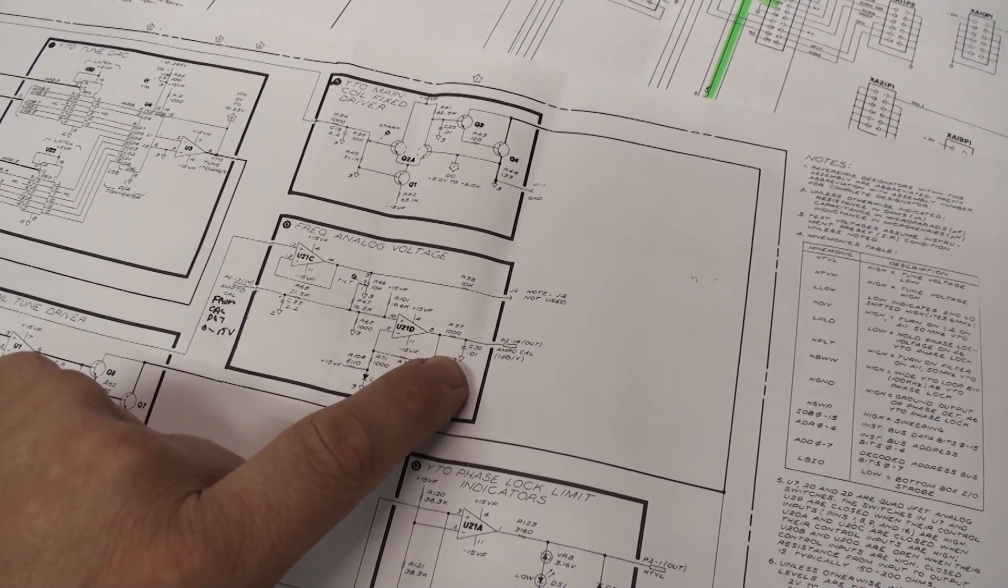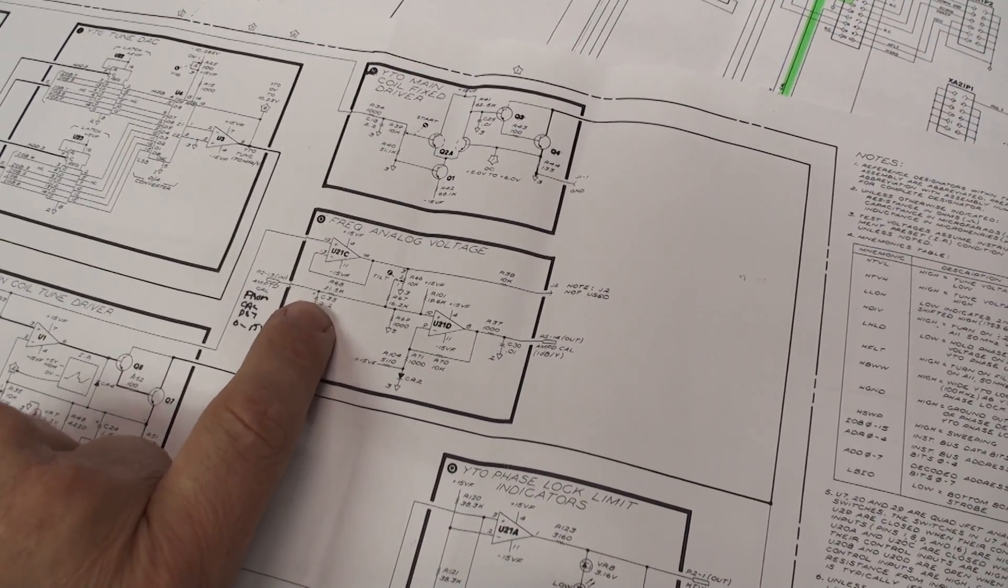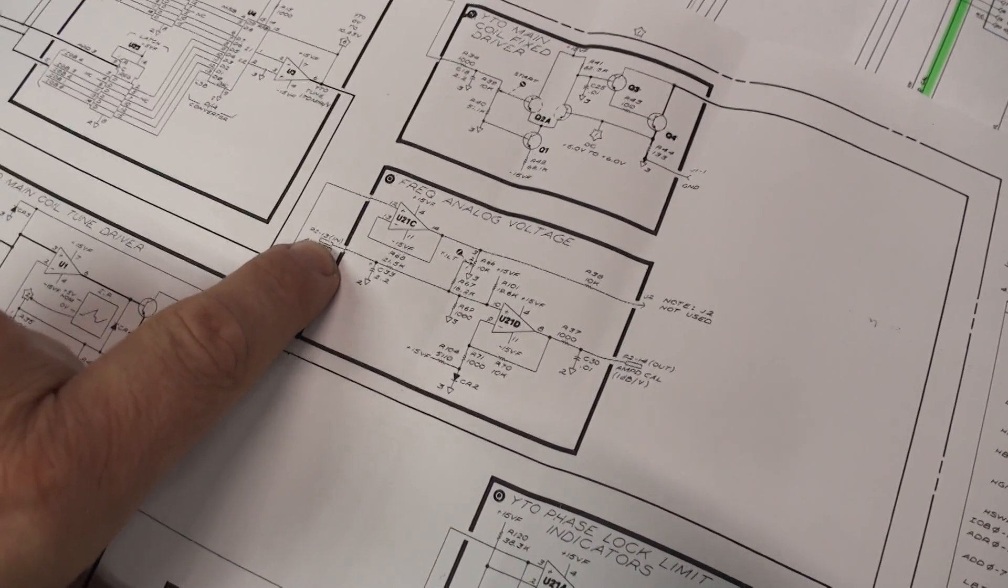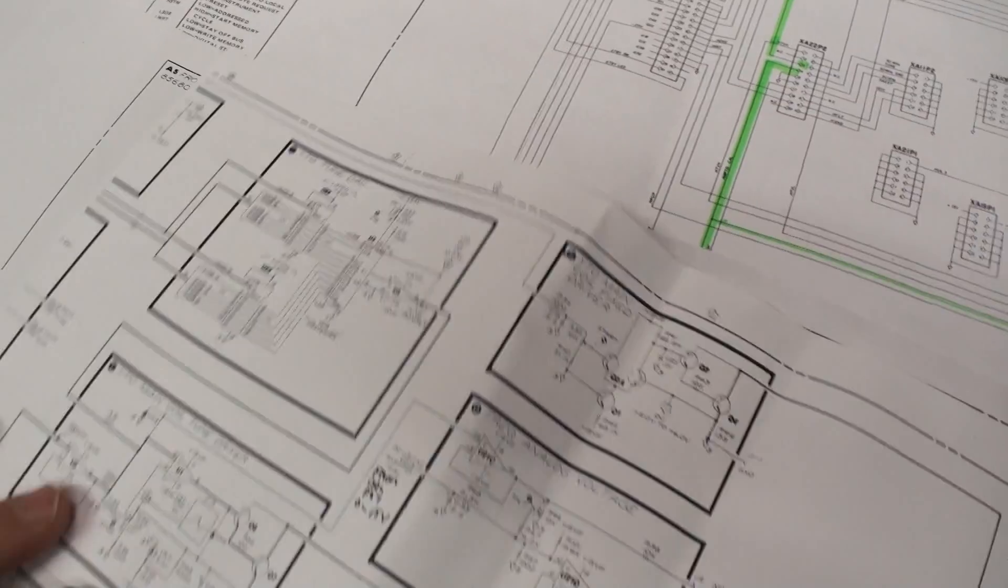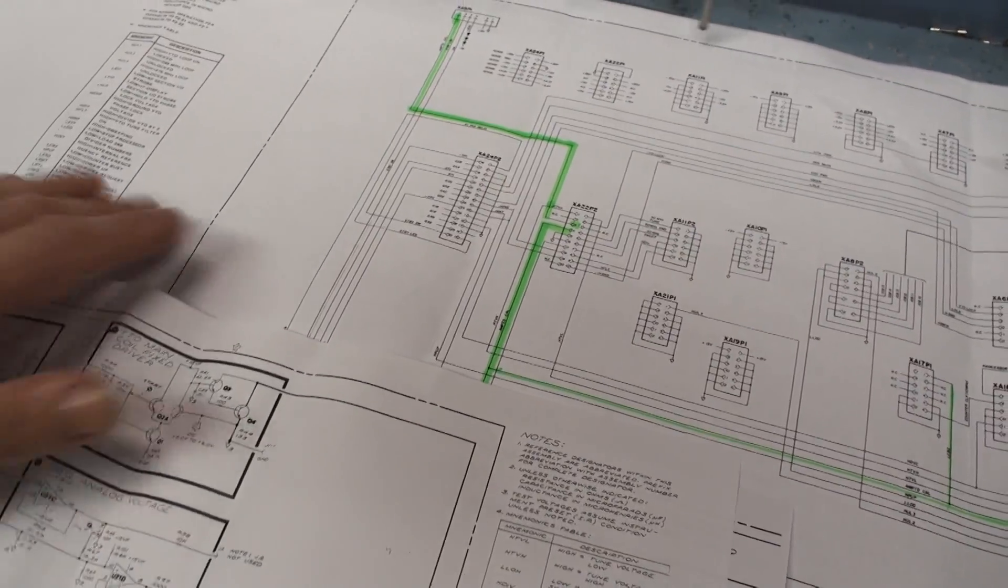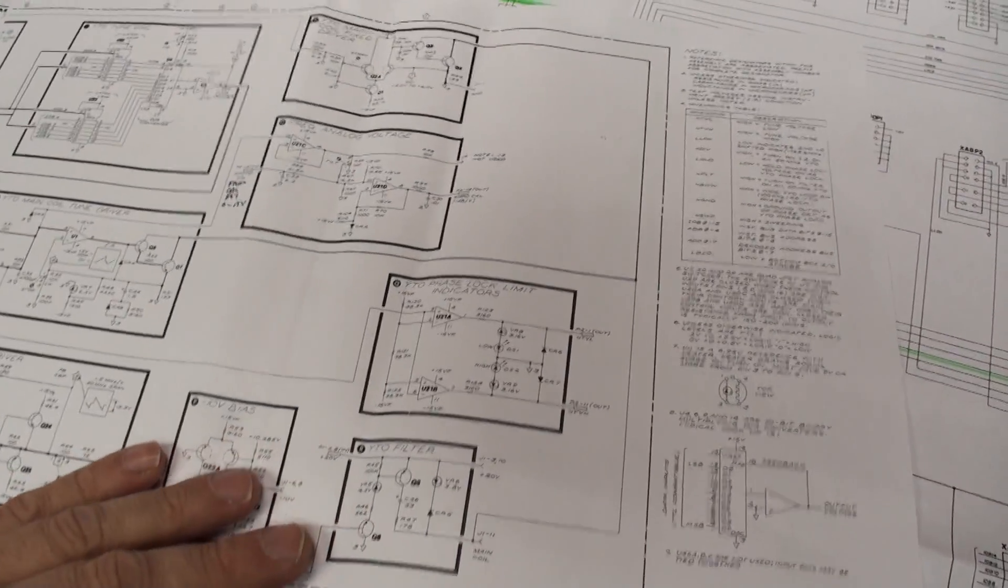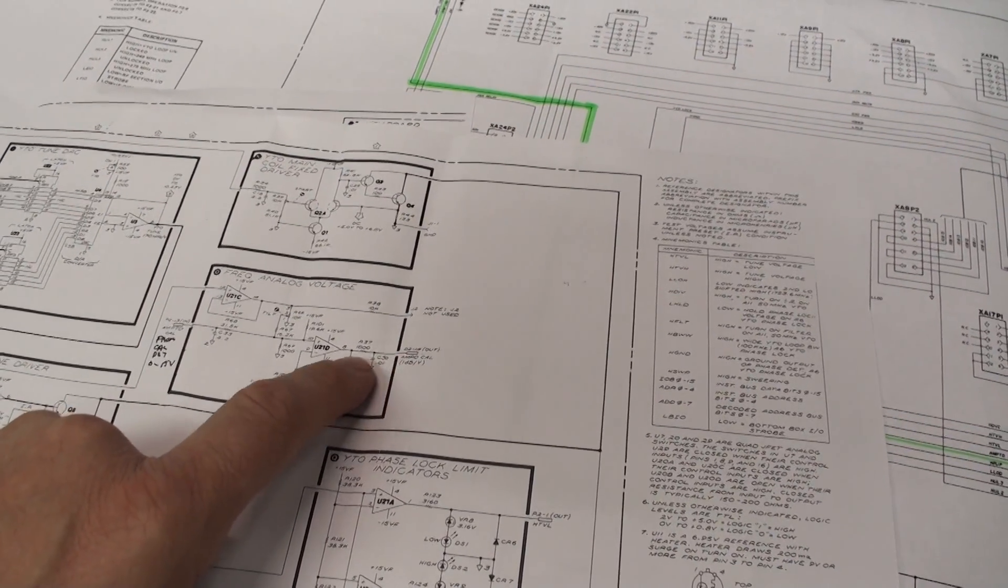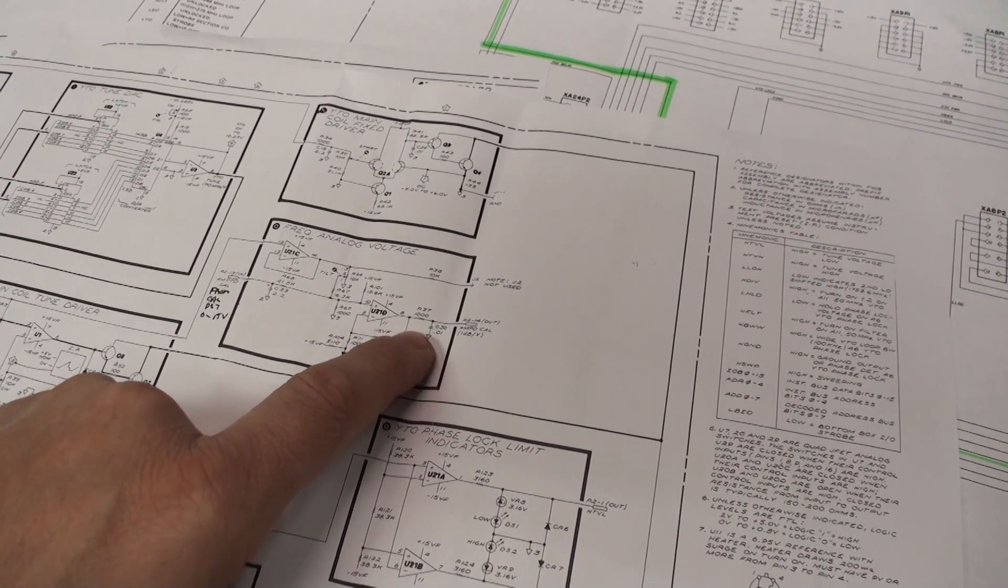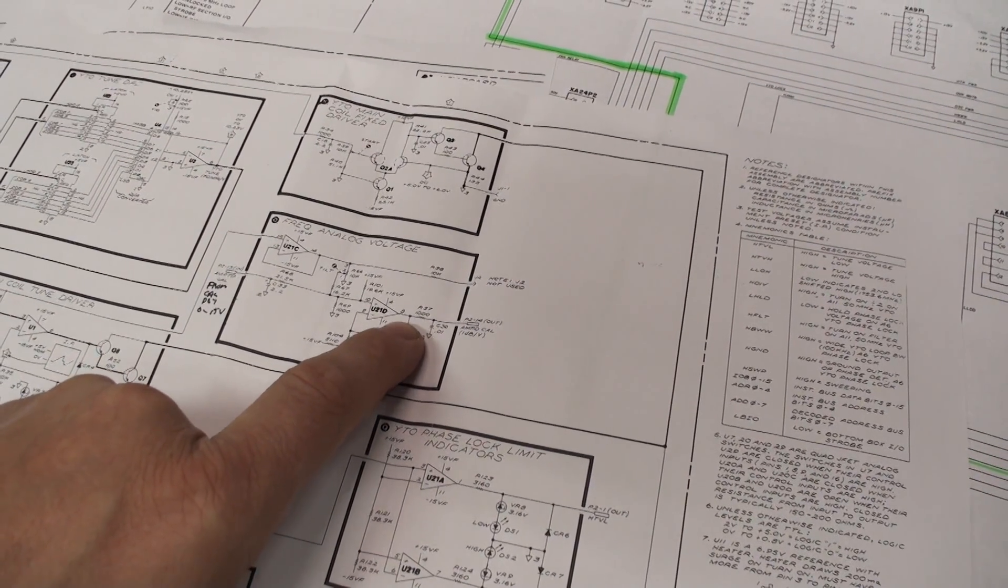So the first thing I need to do, I think, is to just possibly with an ohmmeter and probably do some static checks. Put an ohmmeter on between pin 10 of this chip. Or even pin two, pin 13 on socket two of the board underneath. And ohm it back to the pot. Now, I don't know how easy that's going to be because that means I've got to remove the front panel again. And the unit's in situ at the moment. But what I can probably do is buzz it through to the motherboard. So I'm going to do that, and ascertain that there is actually some sort of physical connection. There's not like a bad joint. And then have a look at the output of these, this op amp and see if this level's changing. I expect a level shift on where it looks like pin 8. And I'm hoping maybe if I look underneath there'll be some sort of test point.